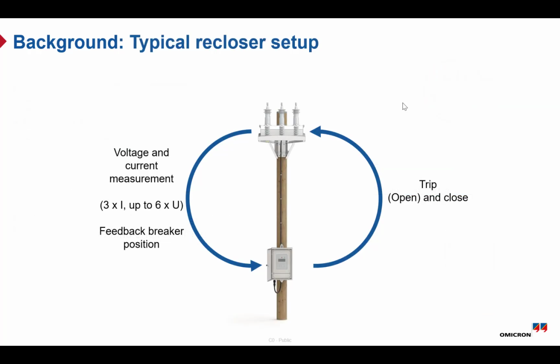Now, let's look at a typical recloser setup focusing on the signal exchange between the controller and the circuit breaker and why this is important for testing. At the core of this setup is the control cable. This is the main link between the recloser on the pole and the controller. During testing, we completely isolate the controller from the real system. We disconnect this control cable and connect the test set instead, so the controller only sees simulated signals. That's why it's very important to understand what signals are actually passing through this interface.